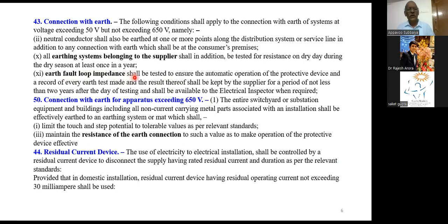This is what we are going to treat in the domestic premises. I'm again saying our concern is in the domestic and distribution sector where accidents are more. We are not going for the complex nature of installations that can, for example, be EHV installations or GIS substations. We are not touching those areas. Of course, if the connection exceeds 650 volts, there is the same requirement for the entire switchyard or substation.